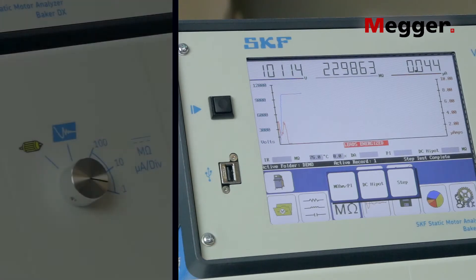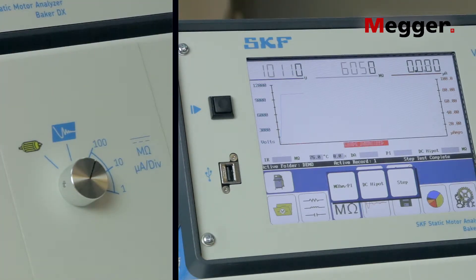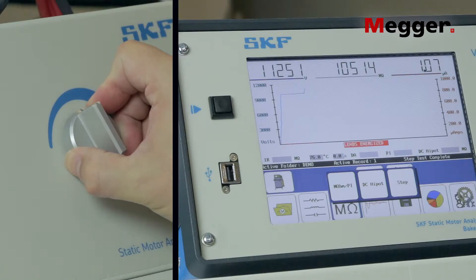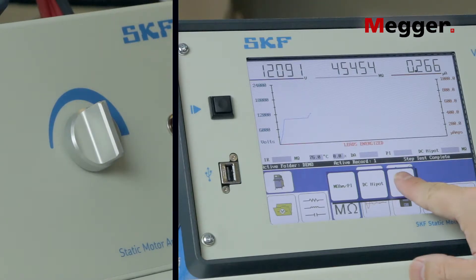When the step timer is complete, return the power pack's function knob to 100 microamps per division. This will avoid an overcurrent trip when you increase the voltage. Turn the voltage control knob smoothly to increase the voltage to the next desired level, and press step.